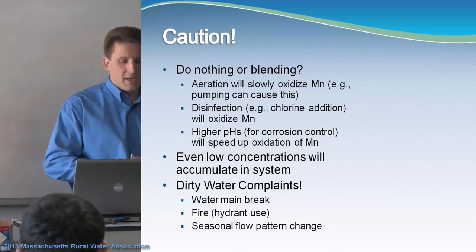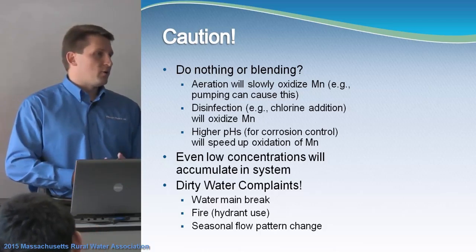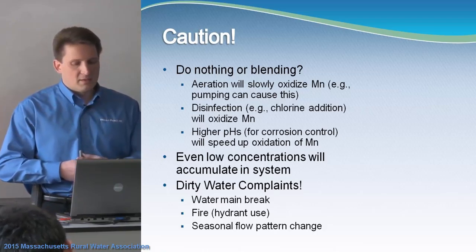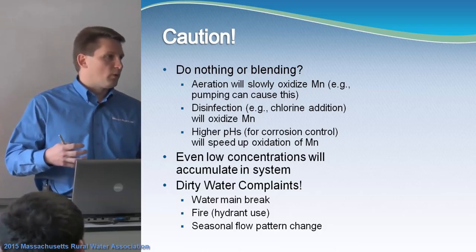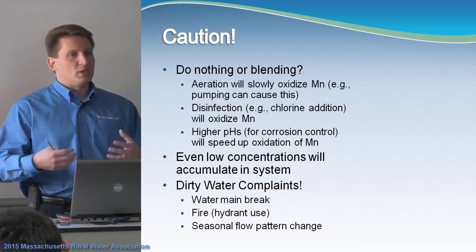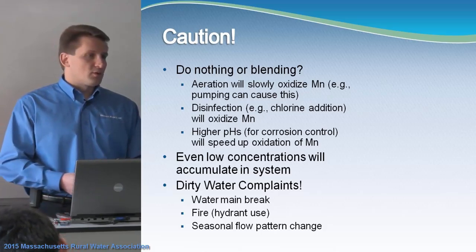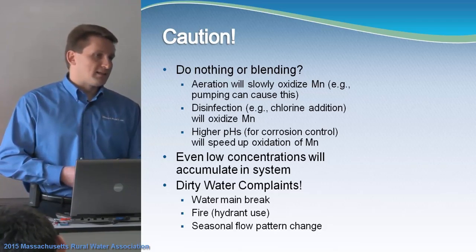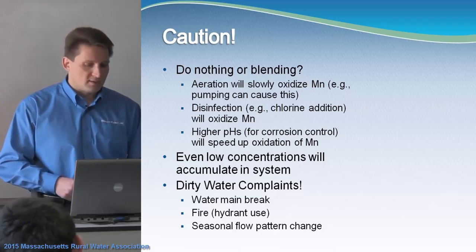A word of caution regarding the 'do nothing' or blending scenarios: aeration will slowly oxidize your iron and manganese. Sometimes pumping causes this through turbulence at the wellhead. Disinfection itself — chlorine, whether chlorine gas or hypochlorite — is an oxidant. If you chlorinate your water and you have iron and manganese in there, you will oxidize it and it will turn into that black mess. Higher pH also accelerates oxidation. If you're doing aeration or disinfection and raising the pH, you may be making the problem worse or accelerating it in the distribution system.